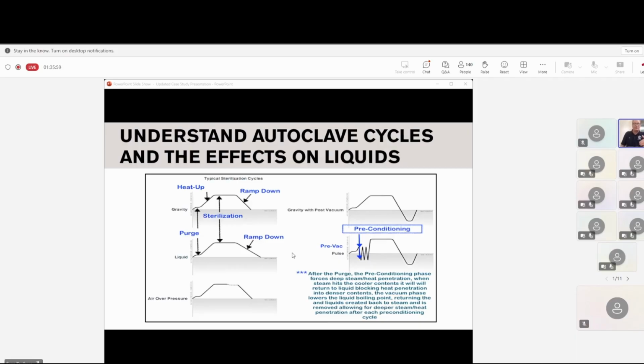So the purge will open the drain valve and it pours steam in, and then it starts preheating the chamber, the contents, the drain, and gets rid of any cool spot and forces it down the drain. So it's preheating everything. Now, when it goes into the heat up, you'll notice that it's a very slow, methodical ramp up. If you ever hang around to listen to the autoclave, after the purge, you'll hear it go click, click, and you'll hear steam going in, stop. Wait a little bit, steam going in, stop. And what it does is it ramps it up very, very slowly. It is a very, very slow process.